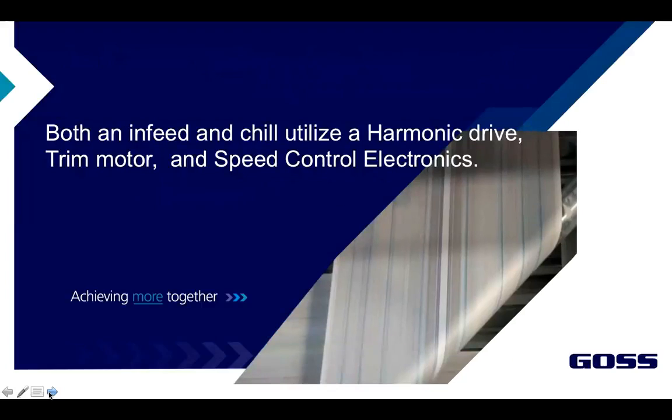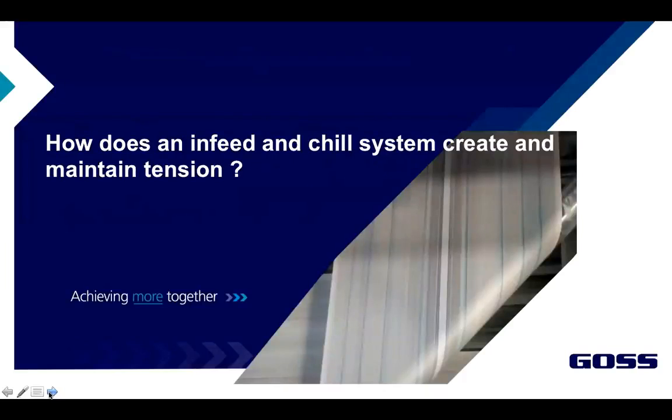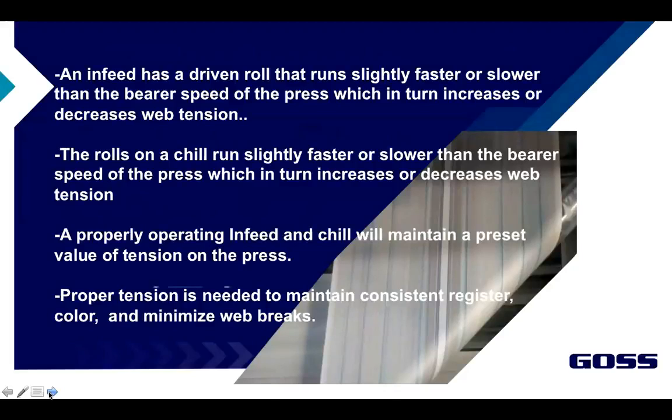Now, an Infeed and Chill that we're talking about utilize a harmonic drive, a trim motor, and speed control electronics. How, through the things we've talked about, does the Infeed and Chill create and maintain that tension? An Infeed is a driven roll that runs slightly faster or slower than the bearer speed of the press, which in turn increases or decreases web tension because you're either pulling harder or not quite as hard. The rolls on a chill run slightly faster or slower than the bearer speed of the press, which in turn increases or decreases web tension.